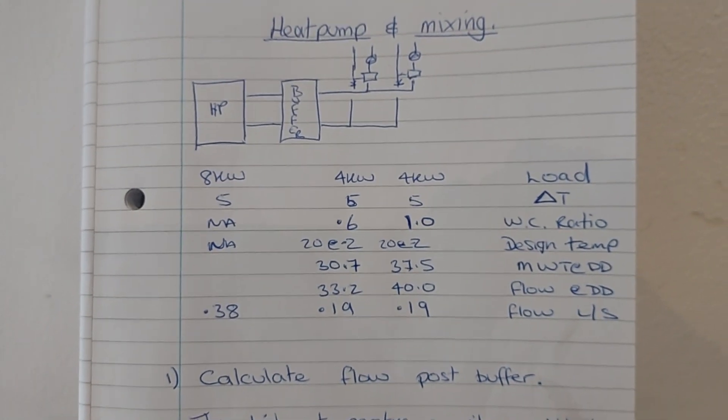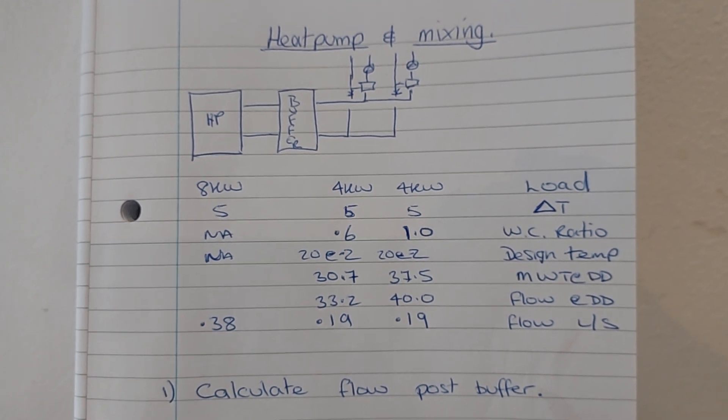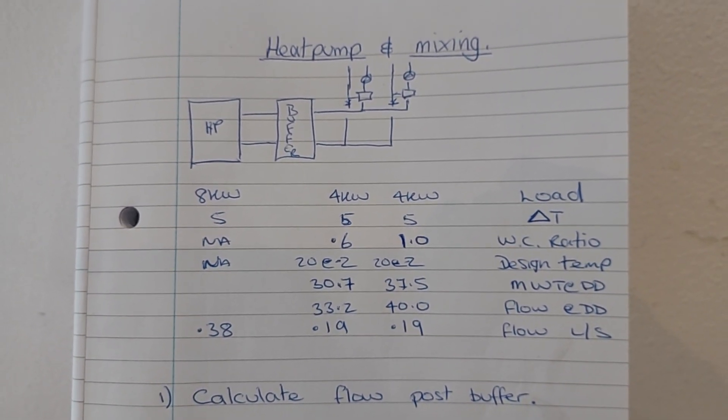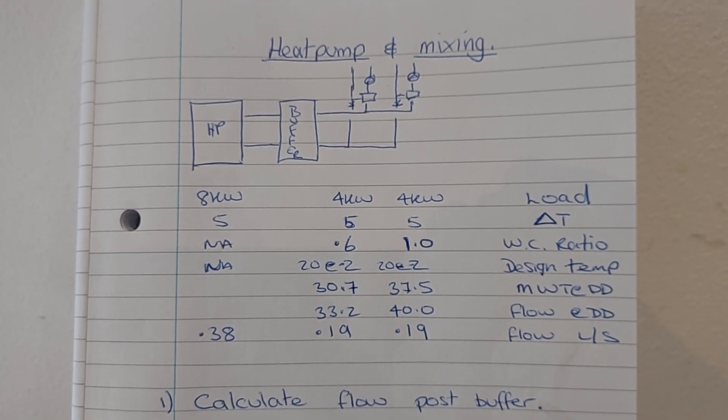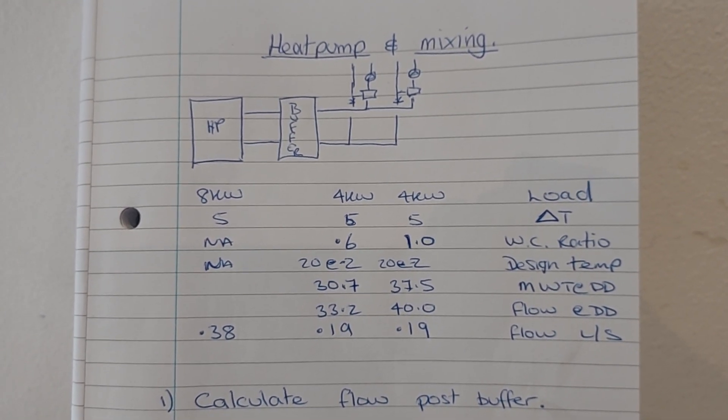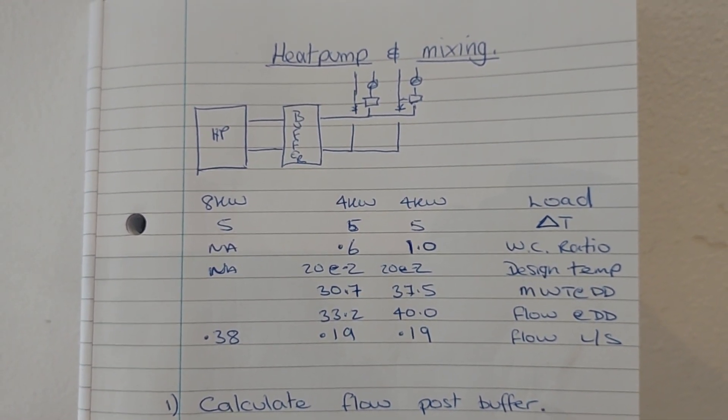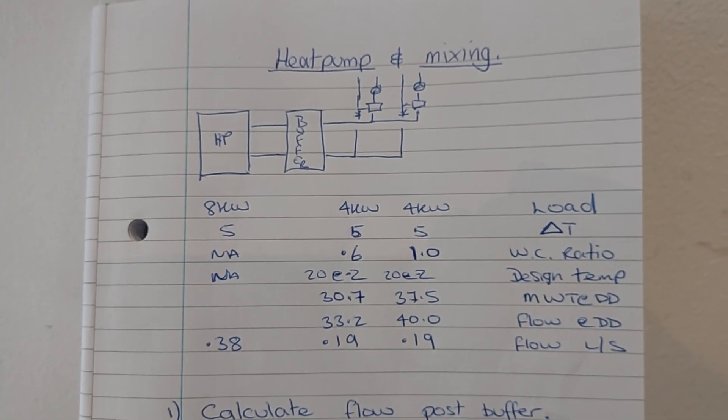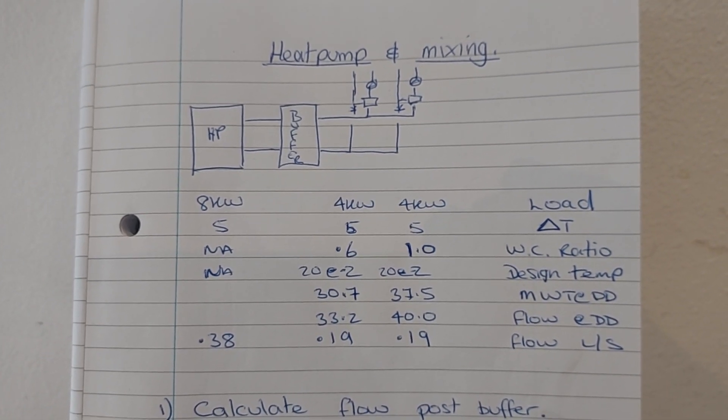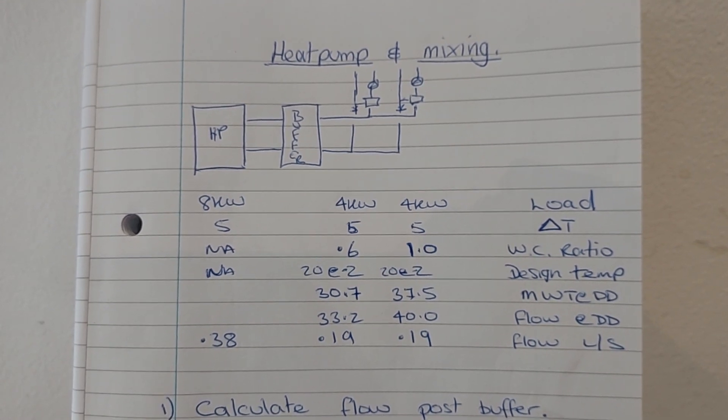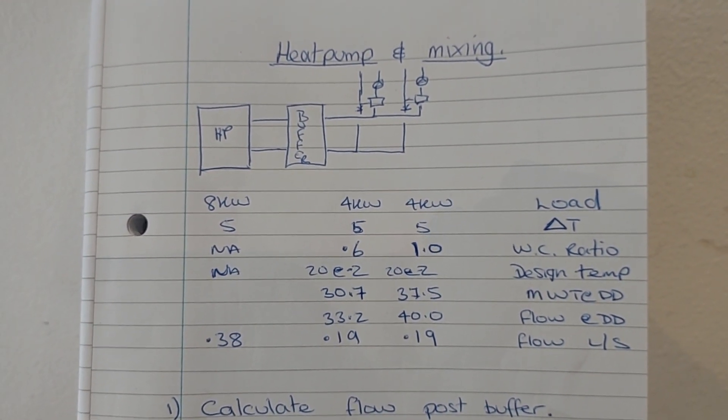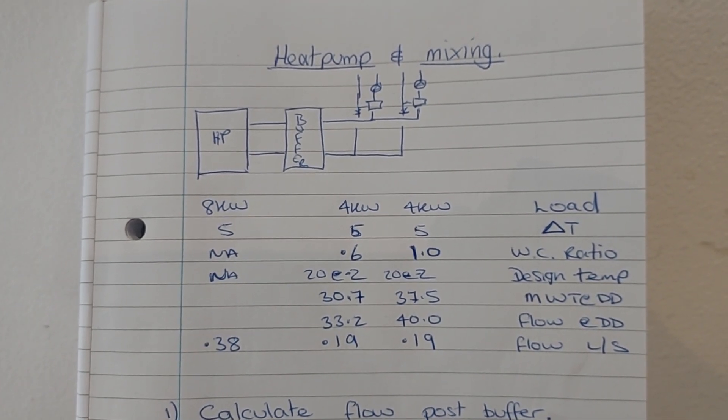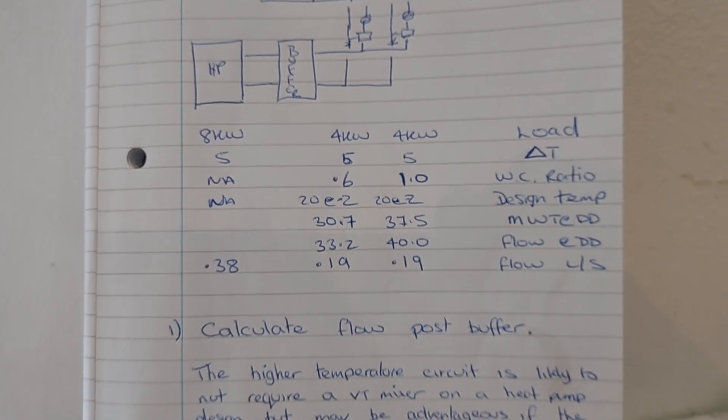It's worth noting at this stage, not all heat pumps have the same strategy and what I've seen quite recently is quite a few of them have delta T pumps, delta T controls and these work very accurately. Our secondary flow rate, however, is likely to be constant. We would have a declining delta T on the secondary side while we have a tightening delta T on the primary side. And so, the flow rate on the primary side would become or always be lower than our secondary side. And this is the whole point of the post, really.